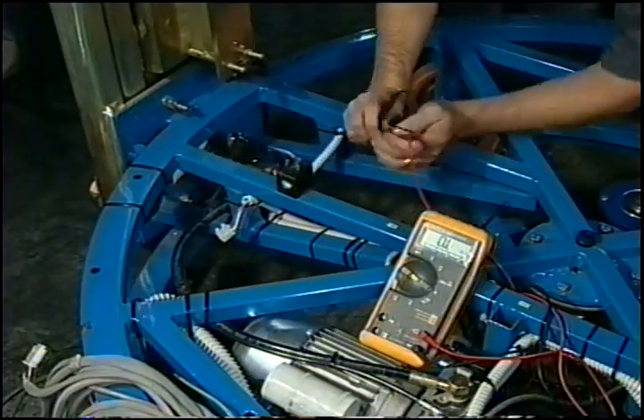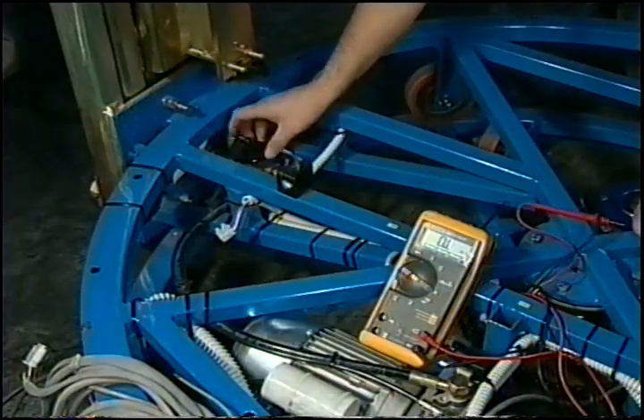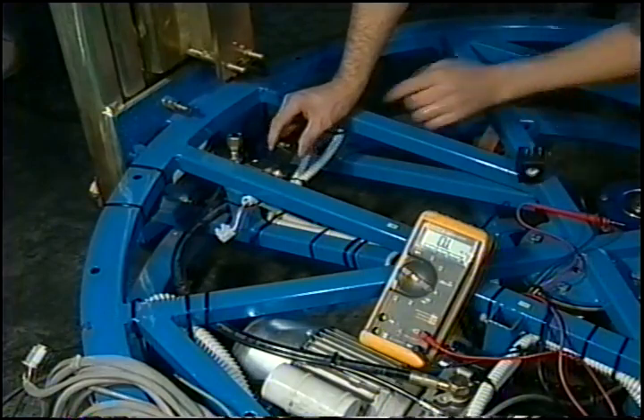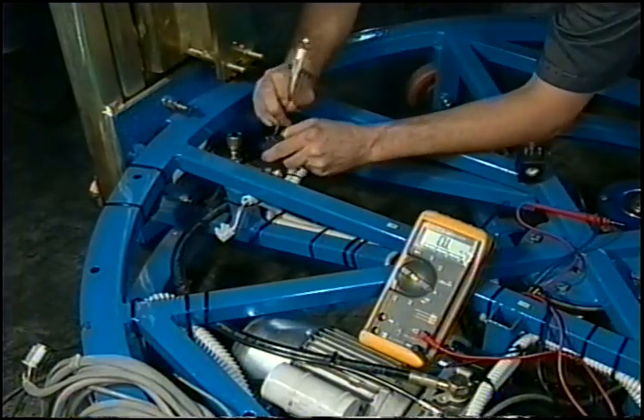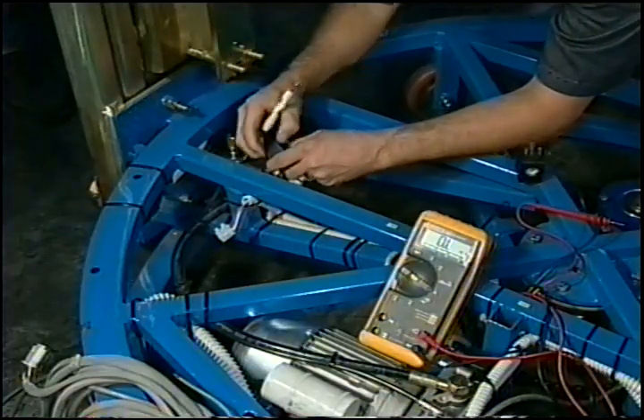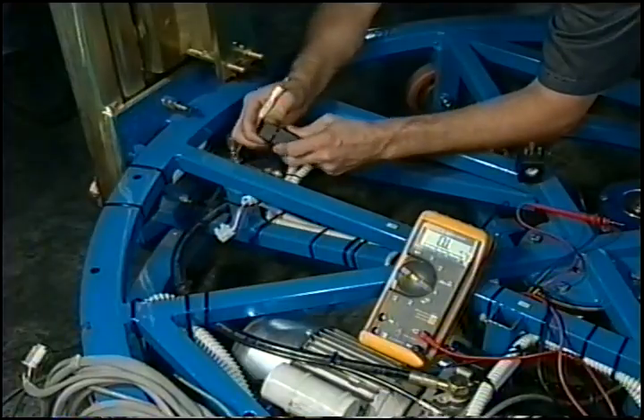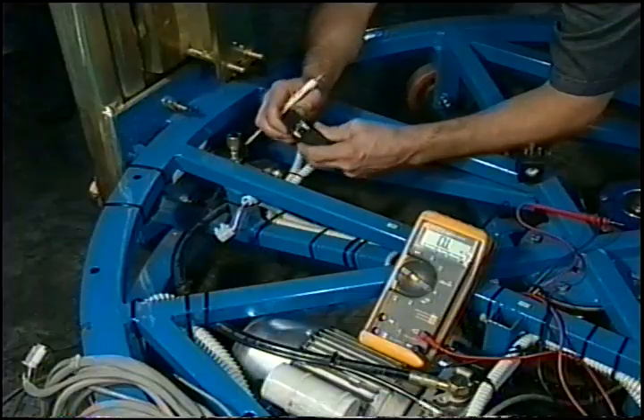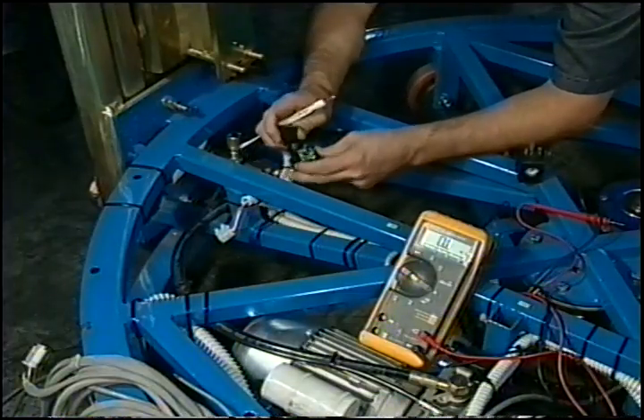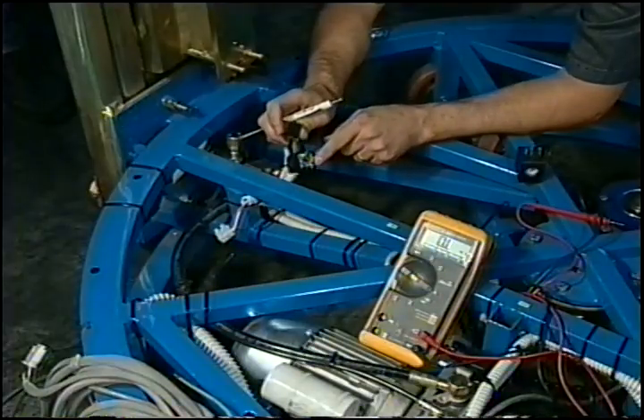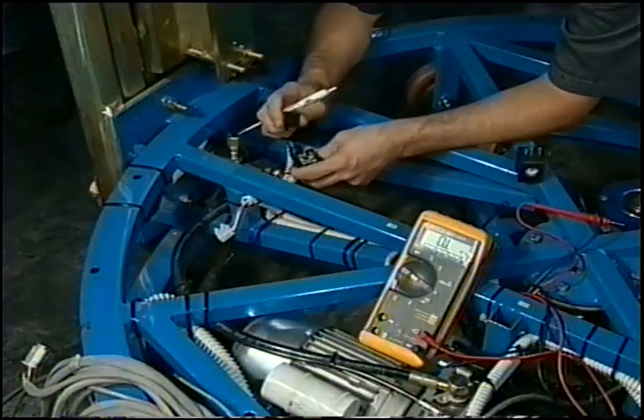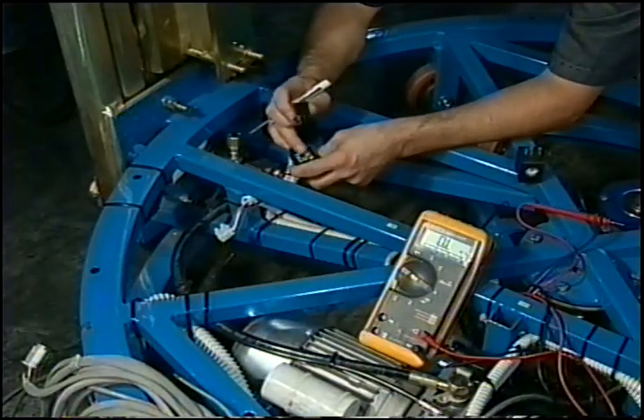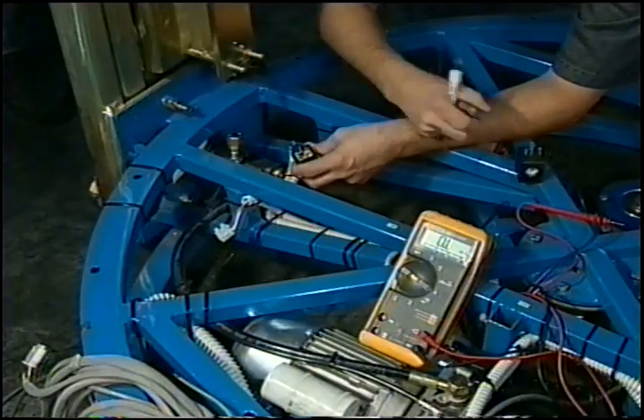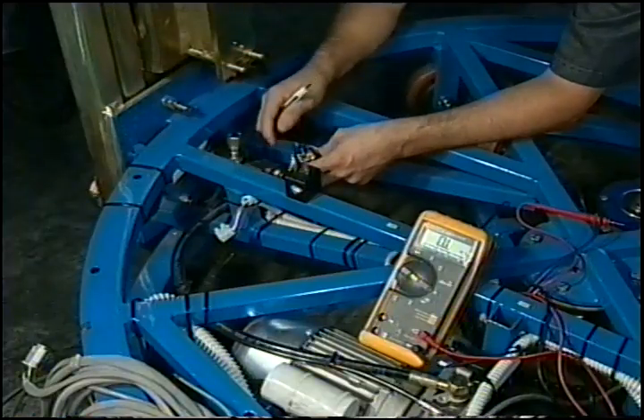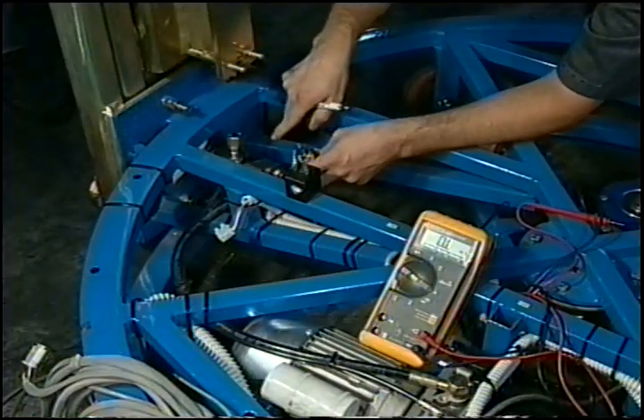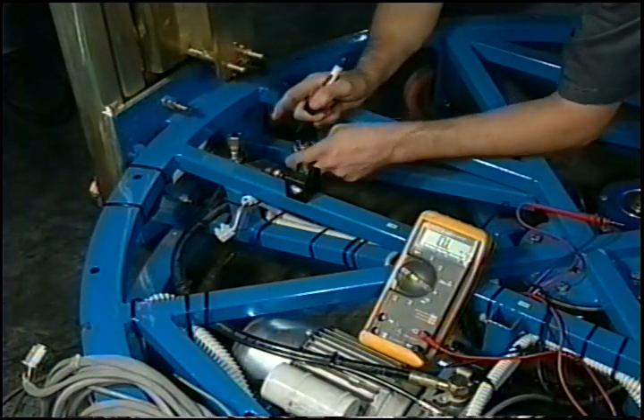Another thing that can sometimes fail on these is, if you notice on the top, it has a diode symbol. And it just kind of pops off much like this. And you have to kind of feed the wires into it from the top. Once you do so, you're going to find that there's a little network of diodes forming a bridge circuit, or bridge rectifier circuit. Sometimes if the diodes fail, you could be getting 120 here, but because the diodes have open circuited, you're not going to get the 120 to the coil itself and make it energize. If it doesn't energize, you're not going to get fluid to your cylinder. If you don't get fluid to your cylinder, your ride's not going to go up.